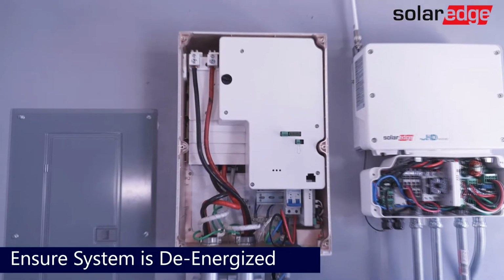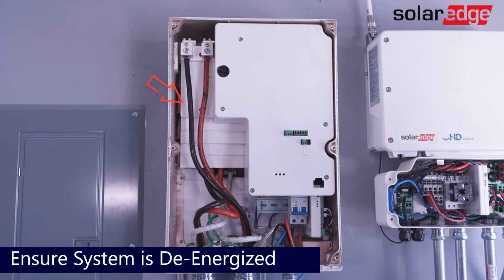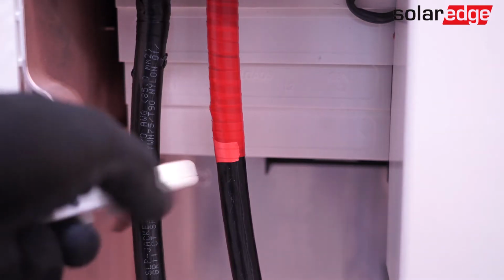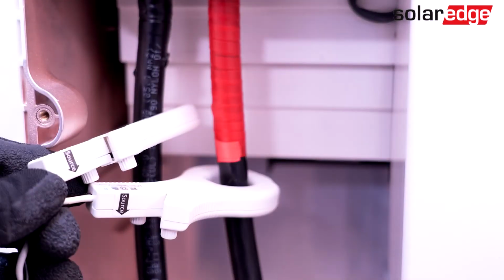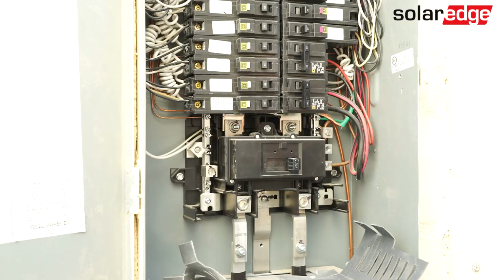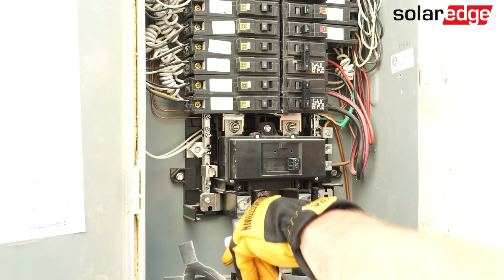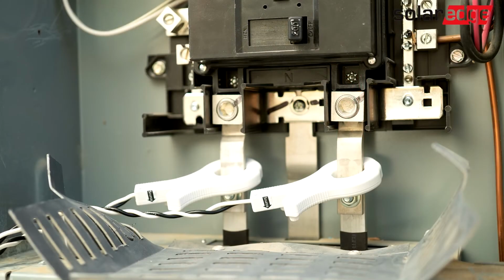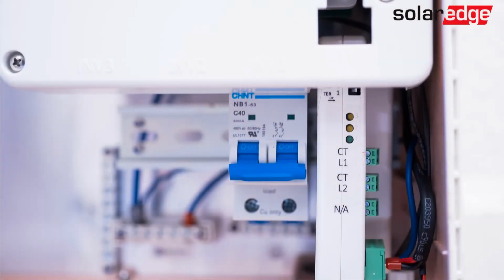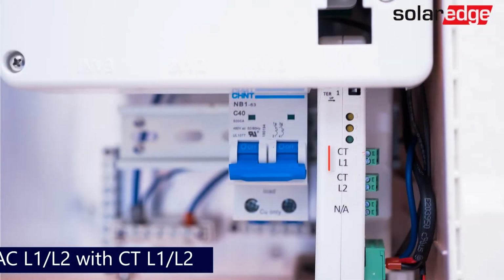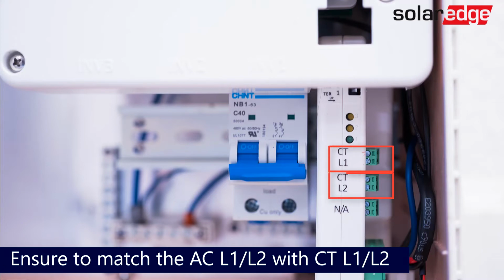For a whole home backup, CTs will be placed on the grid connection conductors with the source arrow pointed towards the grid. For partial home backup, CTs will be placed in the main panel on the service entrance with the source arrow pointed towards the grid. Once the CTs have been installed, wire them to the CT terminal blocks and connect them to the CT Line 1 and CT Line 2 connection points.